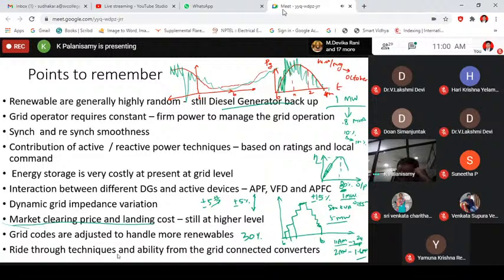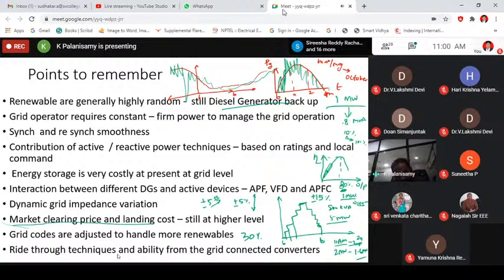See, in a conventional power plant, what we had 10-15 years before is something like this: when there is a fault at a particular point, the energy stored in the transmission and distribution lines, and also the nearby conventional synchronous generators, will supply the fault current. So the current will come from faraway places. Because of that, what will happen? The voltage will drop to a very low level, and it will take some time to restore the voltage to normal, even after the fault is cleared, right?